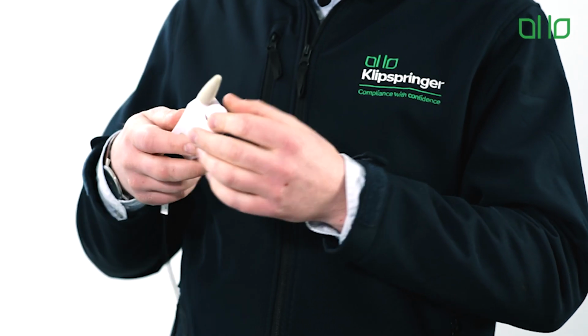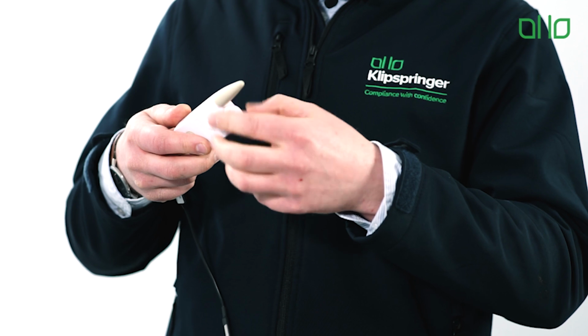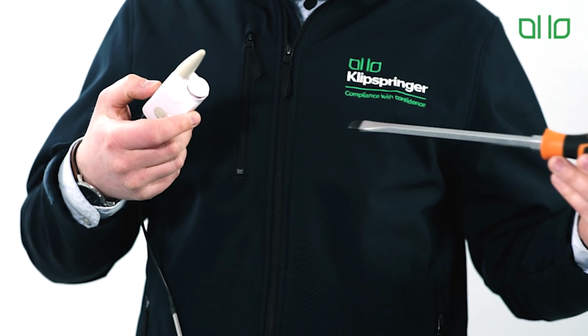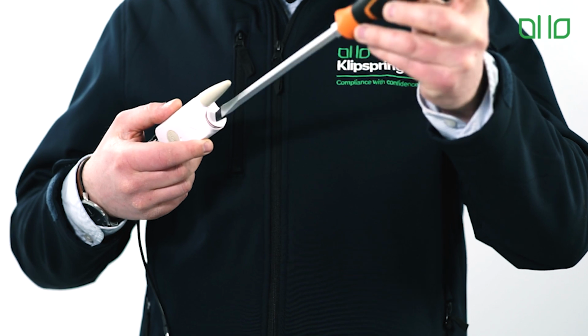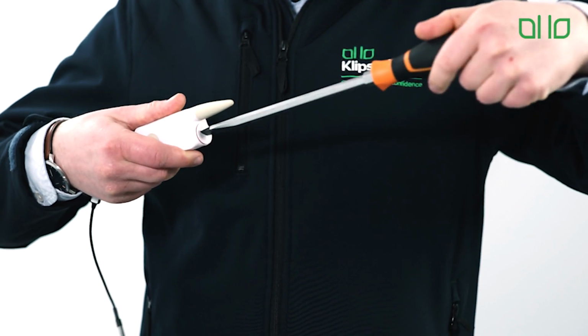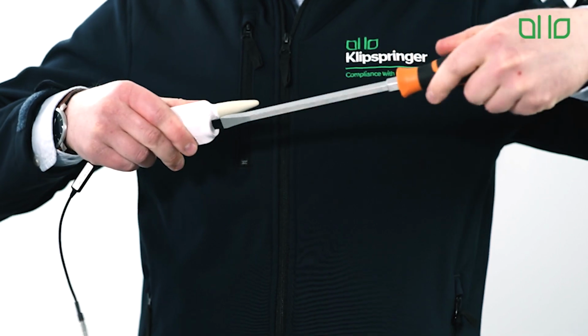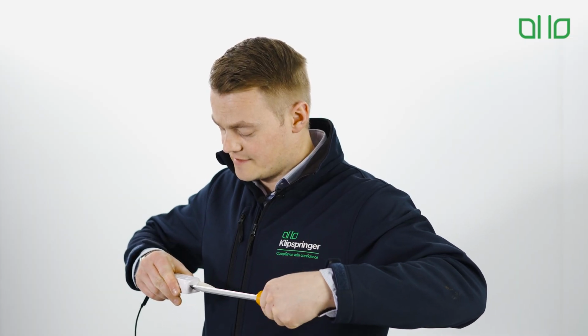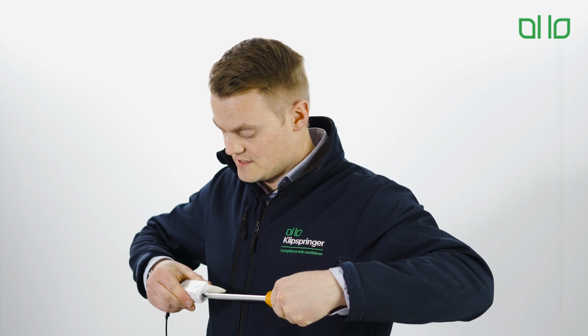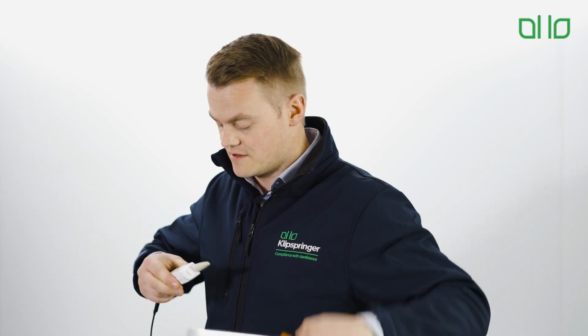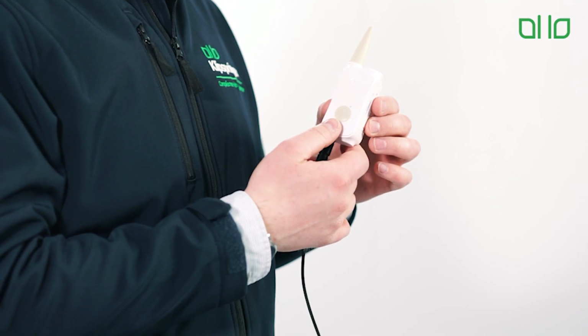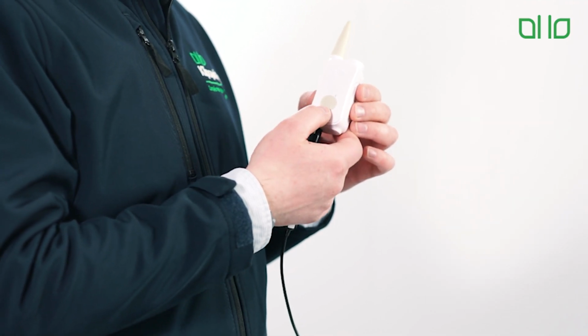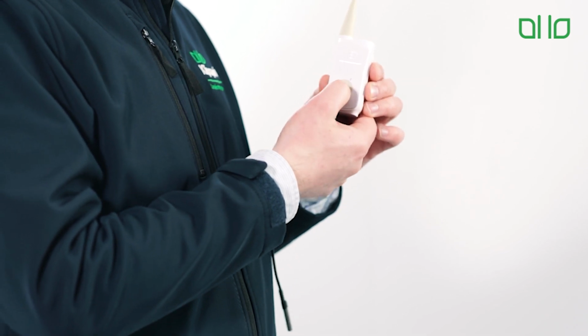To replace the battery, just ensure that the negative side of the battery is facing up. Slide the battery in and replace the sealing cap. Ensure that it isn't cross-threaded before you tighten it with a screwdriver. Again, tighten with a screwdriver, clockwise. It's important to ensure that the sealing cap is done up tight enough so the battery contacts make contact, and also not to over tighten so that you deburr the thread on the sealing cap. To check that the battery has been replaced successfully, press the button once on the front of the transmitter and look for the green light.